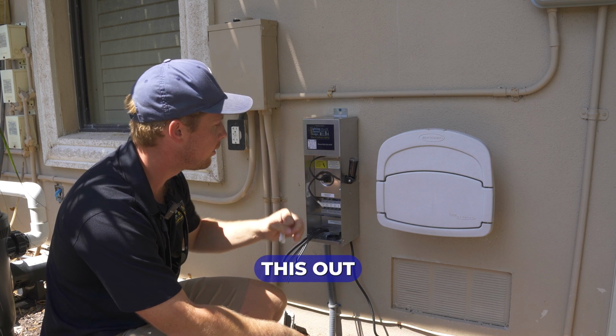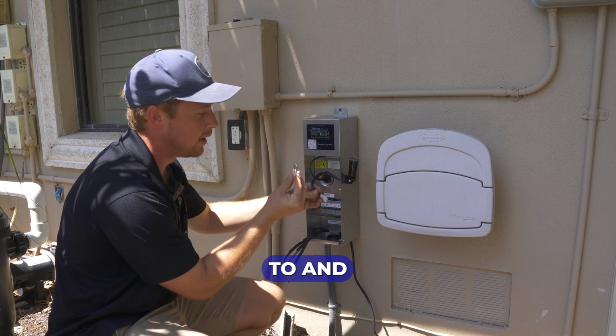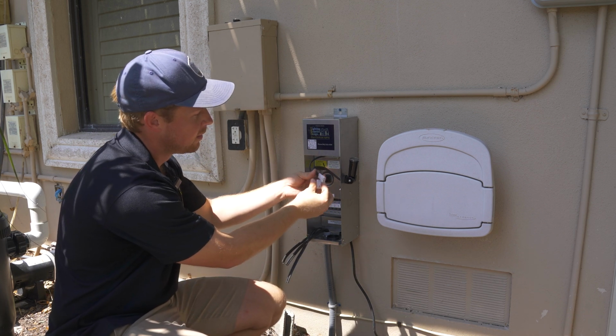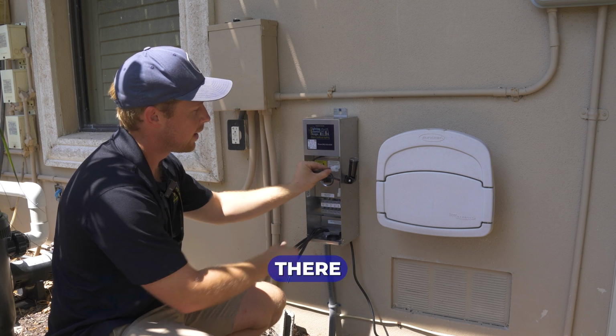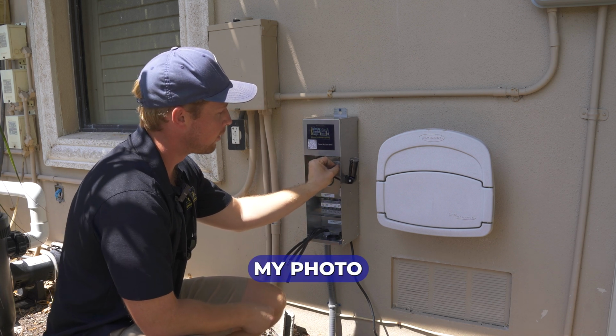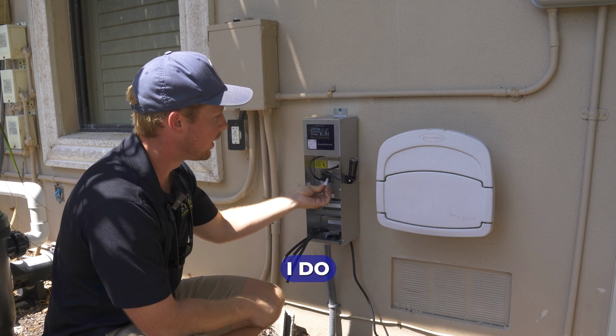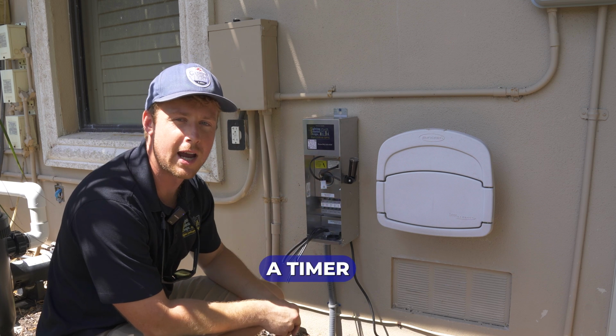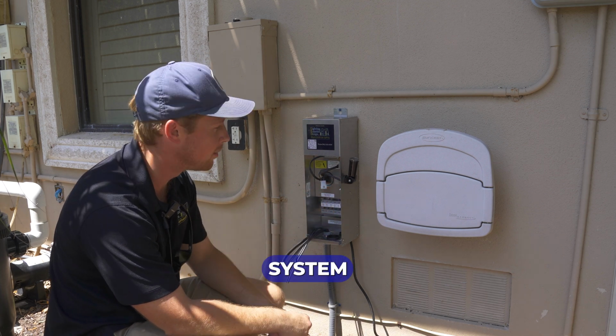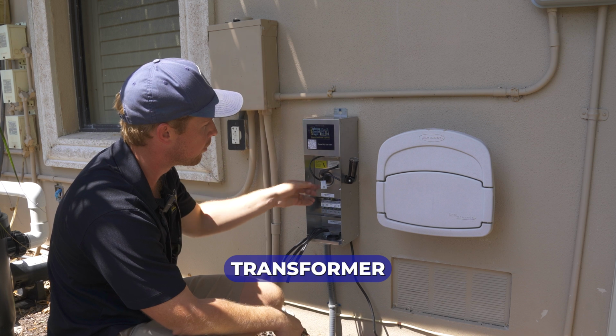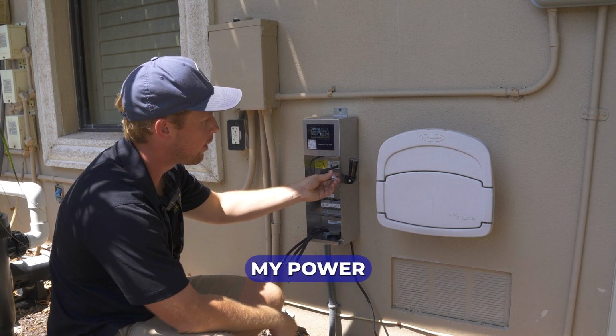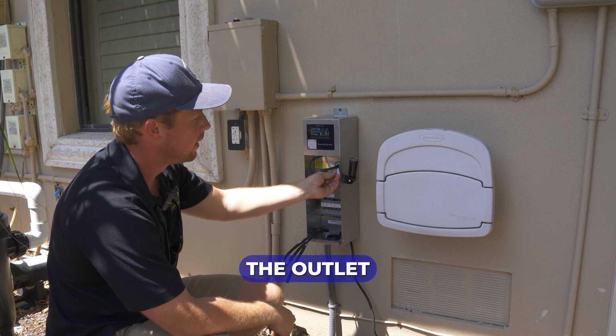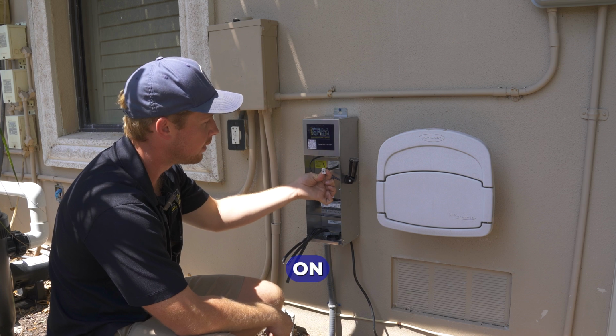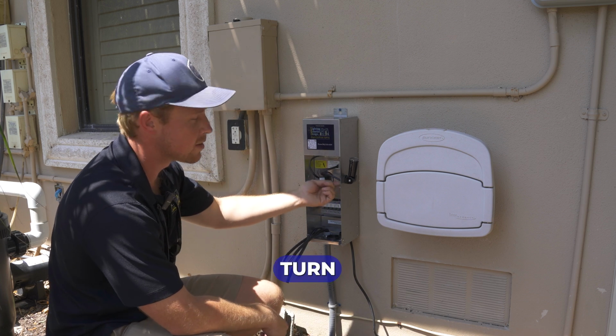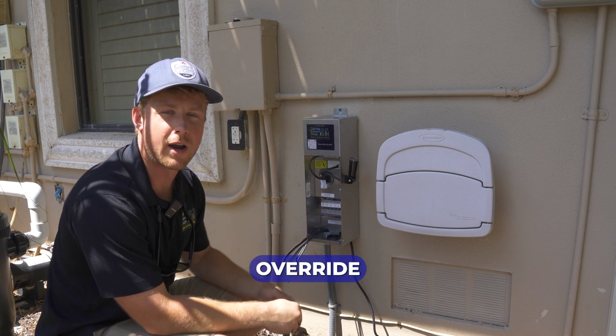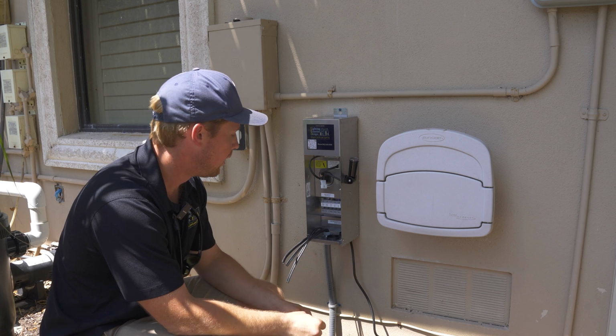We will pull this out. I like to loop that right over to keep things tidy, and then I'll plug my photocell in. The reason I do that is if they want to switch to a timer, or if I want to test the system, I can just open the transformer up, take my power out, unplug it from the outlet, then put this photocell plug on there, plug it back in, turn the system on, and that'll override the photocell essentially.